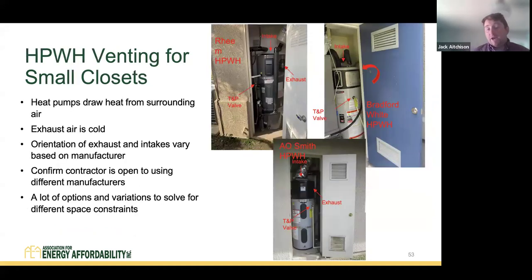So like I mentioned, heat pump water heaters also require fresh air, so our closets are going to be small, typically in a multifamily building. We also need to make sure that we have enough air changes, enough circulation in that closet. One of the ways that we can do that is through louvers - you can see those in the photos here, where we have basically vents for the heat pump water heaters. One thing to note here is the exhaust air is cold, so you have to be considerate of that, especially in an indoor installation.